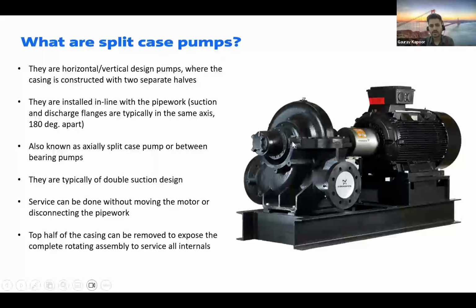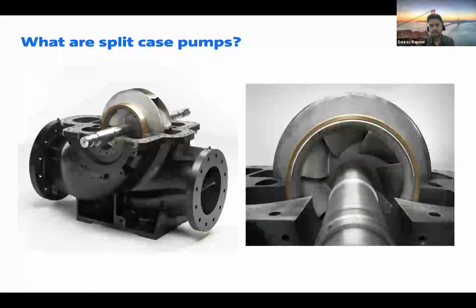They are also known as axially split case pumps or between bearing pumps. You never need to touch the pipes, they are always connected. You can access all the components at the site itself just by opening the half of the casing. Now, this is how the pump looks when you open the top half, or when the split case opens the split casing. You can access the complete shaft arrangement, impellers, wear rings, and the mechanical seals and bearings also.